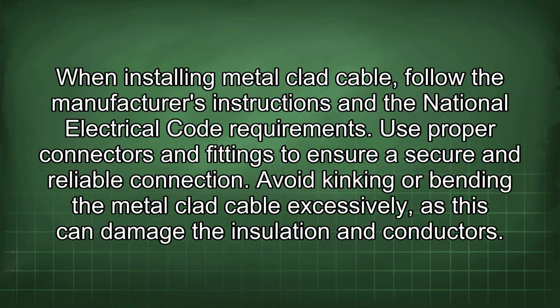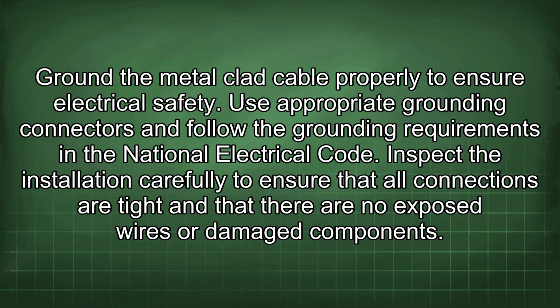When installing metal-clad cable, follow the manufacturer's instructions and the National Electrical Code requirements. Use proper connectors and fittings to ensure a secure and reliable connection. Avoid kinking or bending the metal-clad cable excessively, as this can damage the insulation and conductors. Ground the metal-clad cable properly to ensure electrical safety. Use appropriate grounding connectors and follow the grounding requirements in the National Electrical Code.